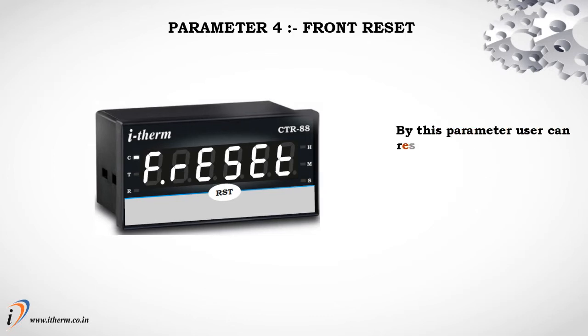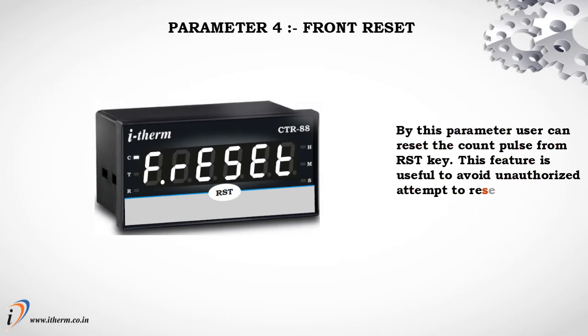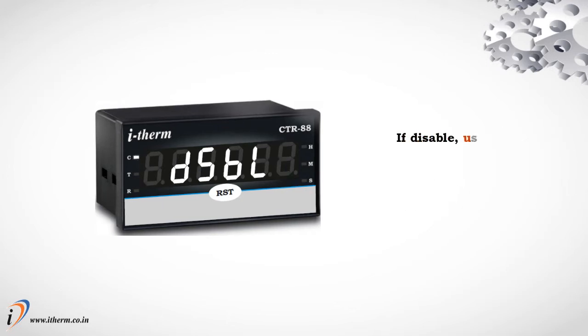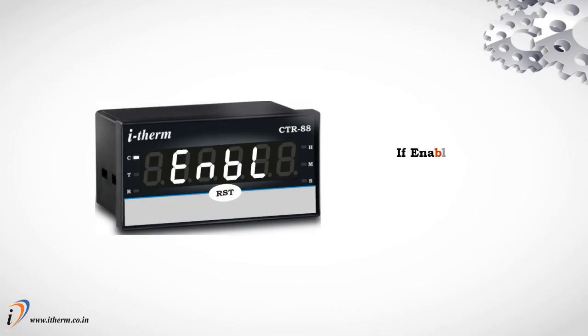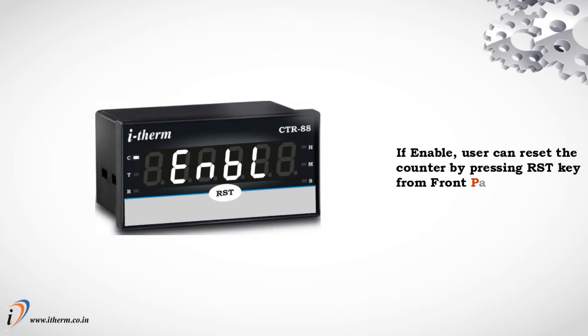Parameter 4: front reset. By this parameter, the user can reset the count pulse from the reset key. This feature is useful to avoid unauthorized attempts to reset the counter during run mode. If disabled, the user cannot reset the count by pressing the reset key from the front panel; only remote reset from the back terminal is allowed. If enabled, the user can reset the counter by pressing the reset key from the front panel.